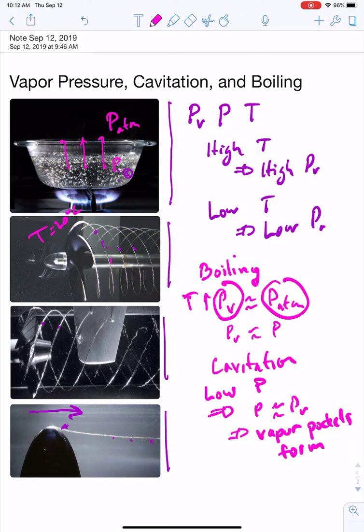Now the danger of cavitation is when those vapor pockets strike a solid object. So this is the danger of cavitation. What's happening here? You're seeing vapor form off of these propellers. It moves with the fluid a distance downstream. And then as the fluid brings these vapor pockets in contact with this solid surface, the vapor pockets collapse. And with the collapse of the vapor, there's just a tremendous amount of energy that's released.